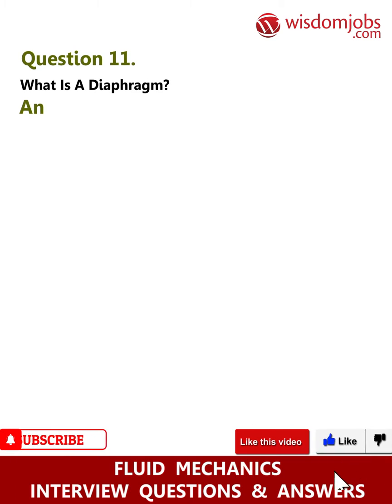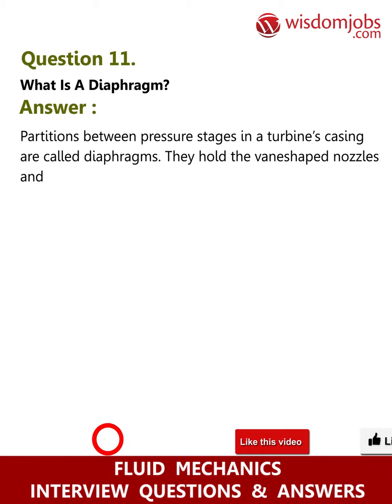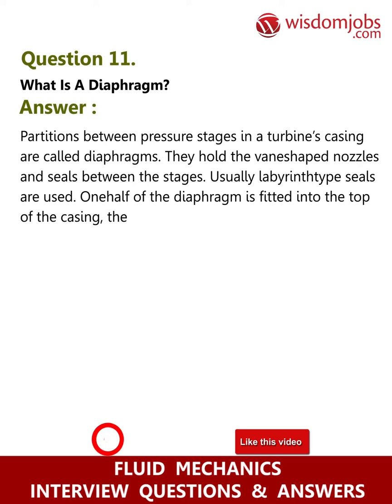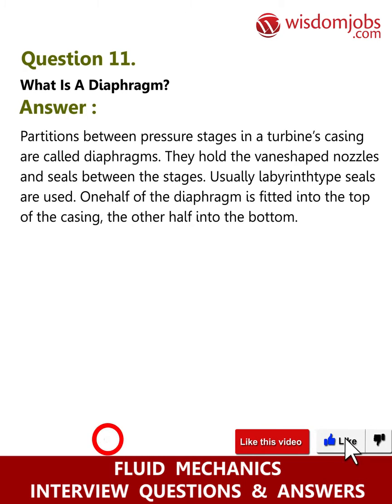Question 11: What is a diaphragm? Answer: Partitions between pressure stages in a turbine's casing are called diaphragms. They hold the vane-shaped nozzles and seals between the stages — usually labyrinth type seals are used. One half of the diaphragm is fitted into the top of the casing, the other half into the bottom.